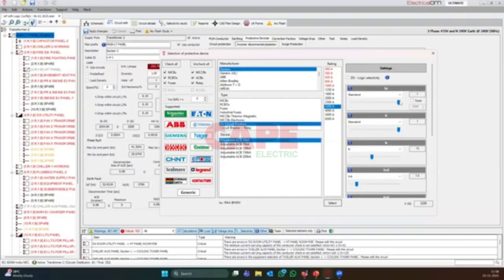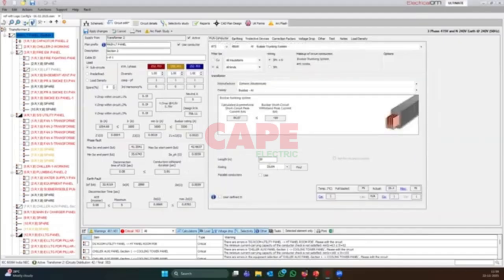But you know what? While doing the actual load, you reduce the load for this specific circuit breaker. Obviously we have all the circuit breakers, ABB, Siemens, Schneider, and all those major brands. You select that specific brand and specific model, you say you're going to keep this model, and you click select. Suddenly, you can also reduce your cable size. You can also reduce the BTS size to something around 1600 amps, and you can click apply.